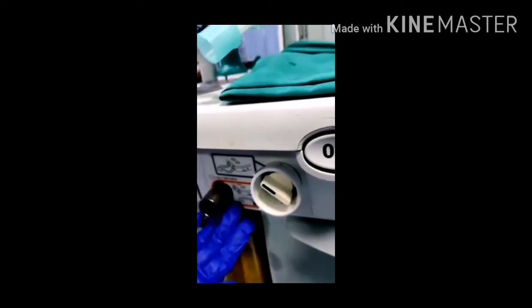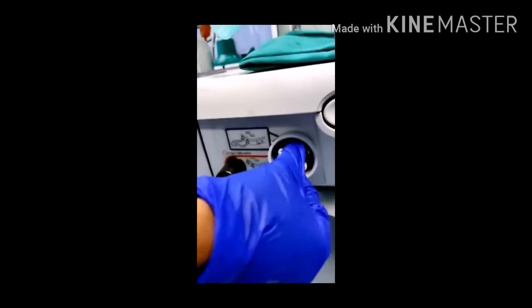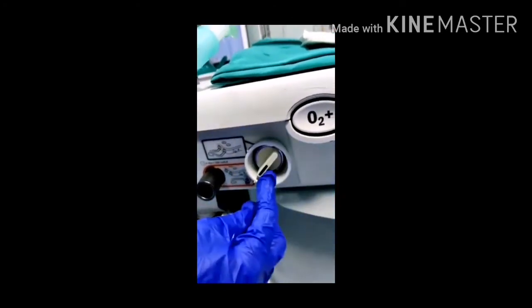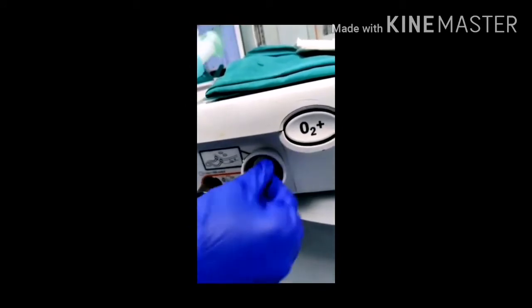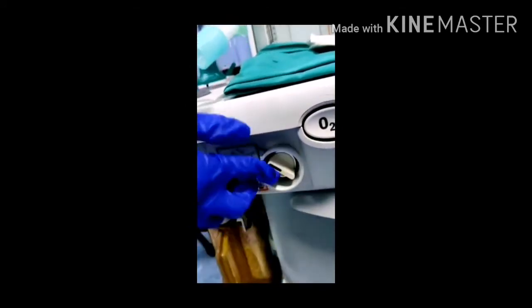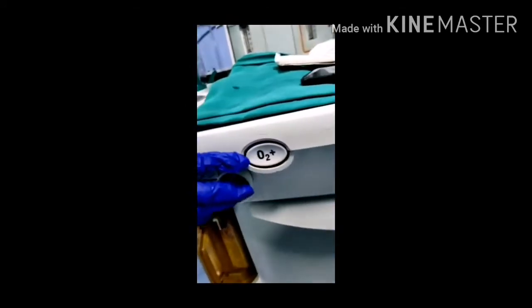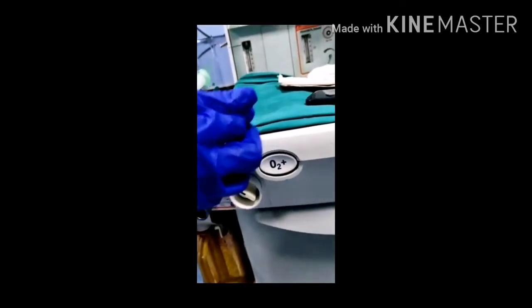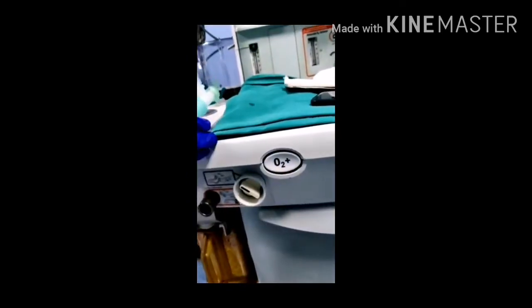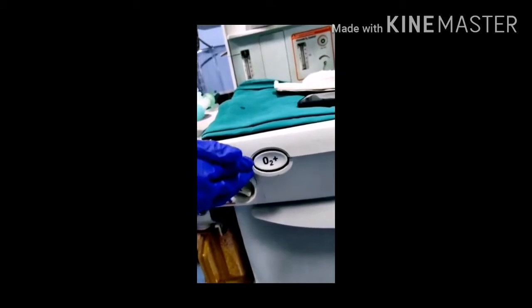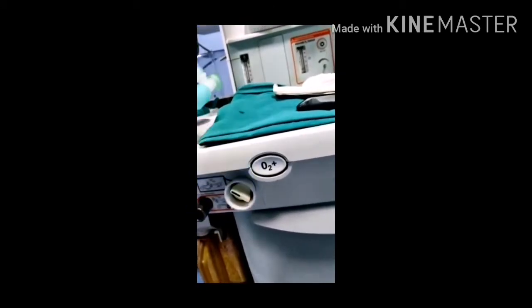When it is single, manual breathing, you just have to turn the circle below. But since we need it on vent, they will open the circuit. This is the O2 flush button, which helps to supply oxygen at a very fast level so that the bellows are not collapsed and are inflated. So we will move ahead.